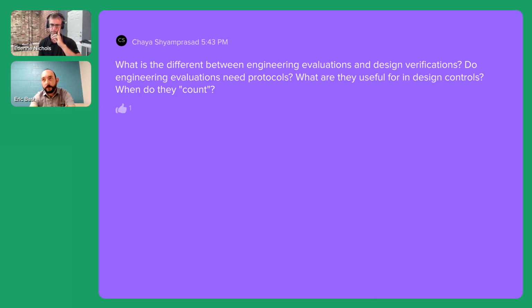Yeah, so best practice is to do engineering evaluations throughout your design process. I talked about using measurement in your design reviews. And one of the best ways to do that is to do some sort of engineering evaluation activities, less formal than design verification, to assess how well the thing you're putting together is meeting your requirements. The earlier you can do that, the better. As soon as you have something that would be even remotely capable of meeting your requirement, put together a simple protocol. You don't even have to release the protocol necessarily, and go execute and see how it does. You want to keep records that you're doing this and put those records within your design history file, but the level of formality does not need to reach what you would do for design verification for those sorts of activities. Okay.